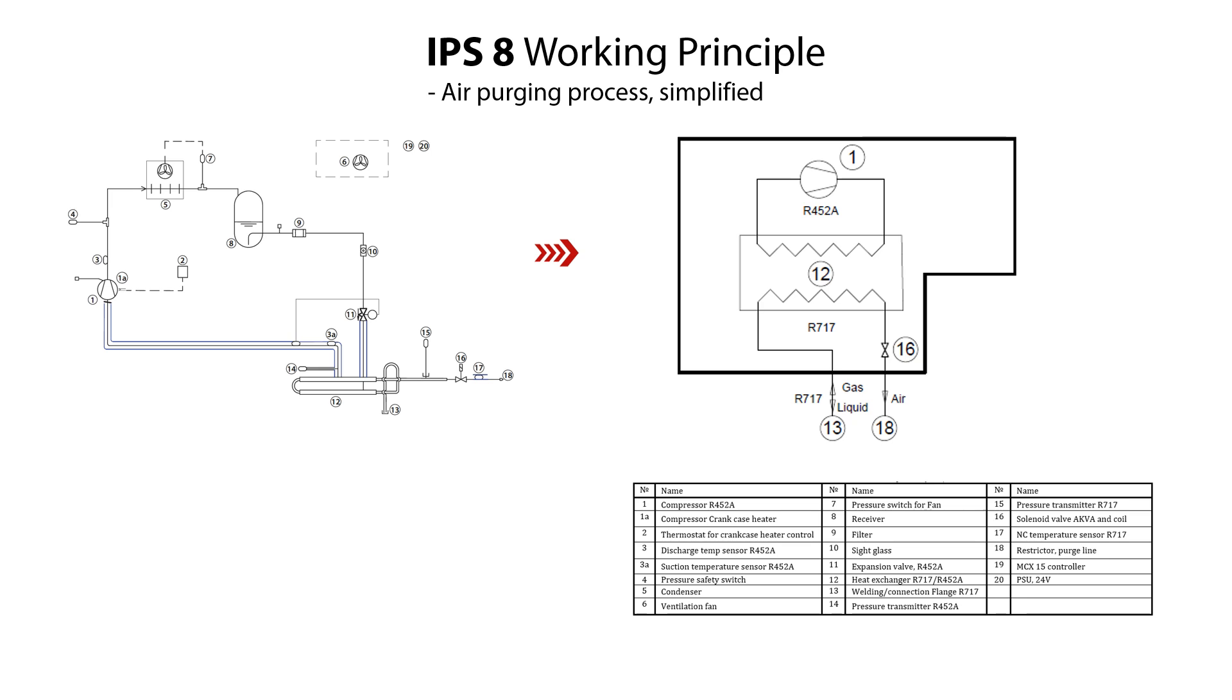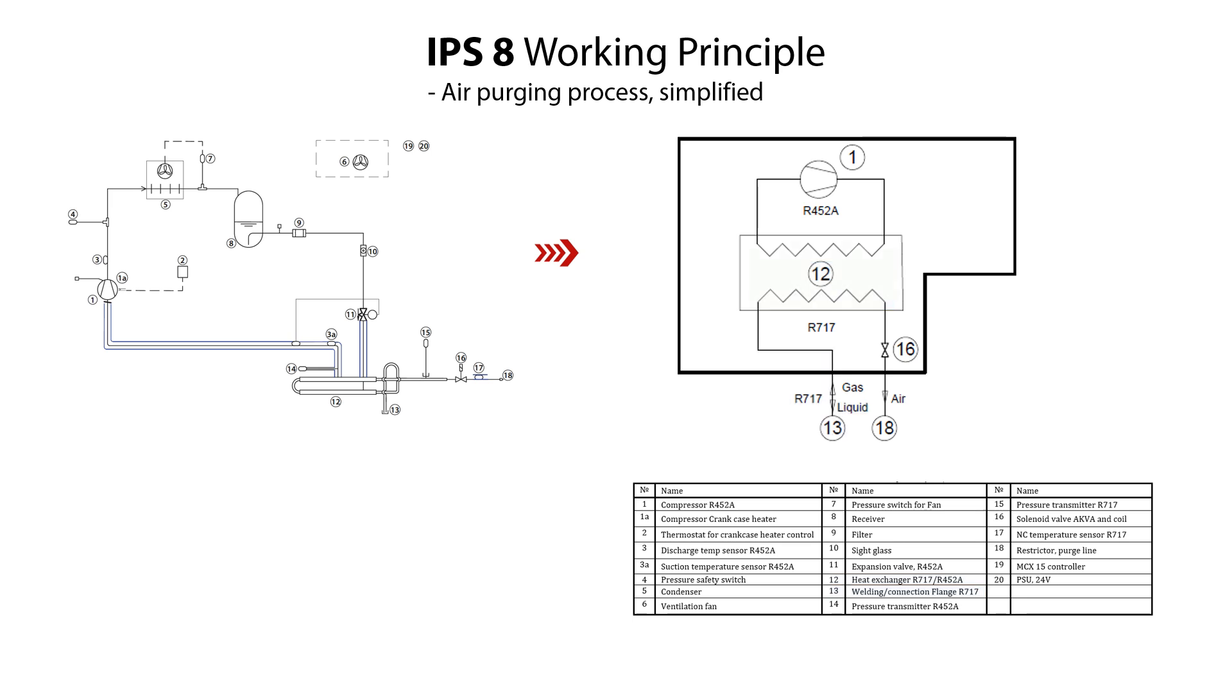The IPS-8 air purging working principle can be described in a simplified way as follows. Gaseous R717 coming from one or several purge points enters through the flange 13 and condenses in the heat exchanger 12, and liquid R717 then returns by gravity through the flange 13. Non-condensable gas accumulates and gradually fills the heat exchanger. When the volume of non-condensable gas increases, then the pressure in the R452A circuit, also called PSAT setting, decreases.